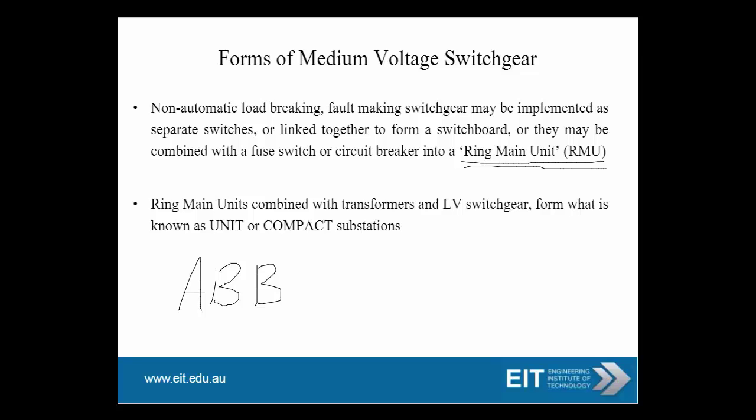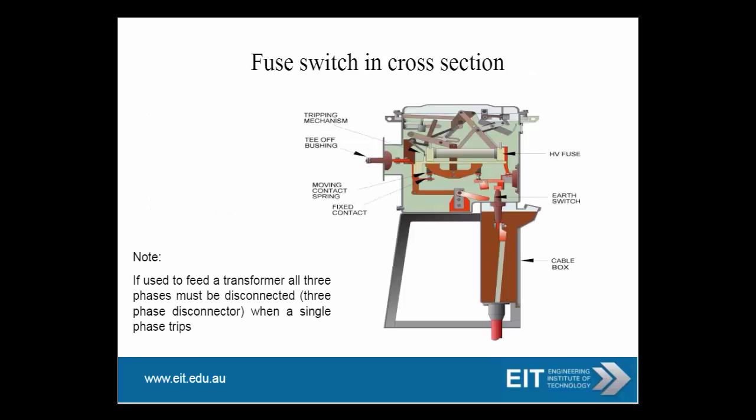On the high voltage end of compact substations, you have your ring main unit. If a switch has to feed a transformer, you can't just rely on the switch for protection — you need a fuse. Internally, the fuse acts as a protection mechanism for the transformer. The benefit of this fuse is that it gives you three-phase tripping: if there is an overload on one phase and that fuse blows, the tripping mechanism trips the other two phases so all three phases open. This prevents single phasing — when one phase blows, all three phases open.